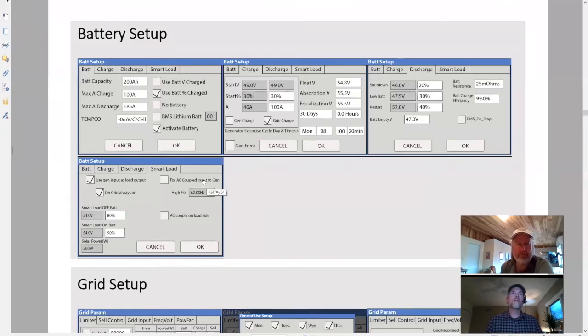Okay, so looking at the setup on the inverter, we'll have you go and change these float and absorption and equalize settings. We're going to turn equalize off, and we'll change those numbers. I already changed the battery capacity and max charge and max discharge.